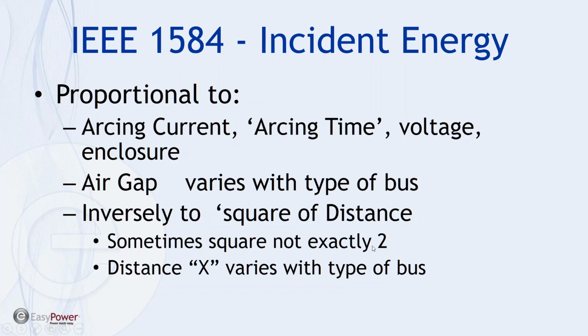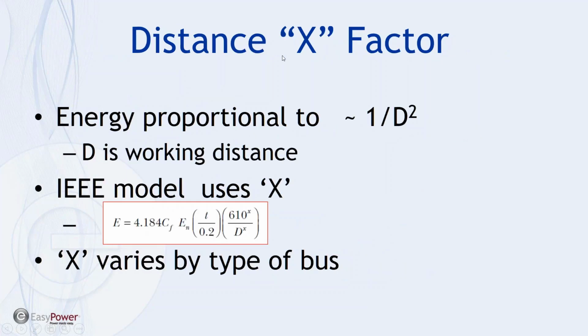Well, it turns out sometimes the square is not exactly 2, and so this brings up what's referred to as the distance X factor. In NFPA 70E, this is discussed as the distance X factor. When they present the equations for the IEEE model, they show for incident energy to use this equation here, and the X in both of these locations refers to this distance X factor, which is a function of the type of bus.